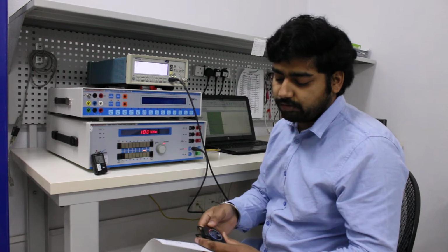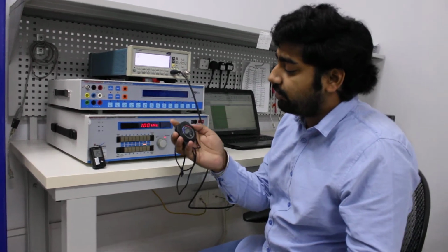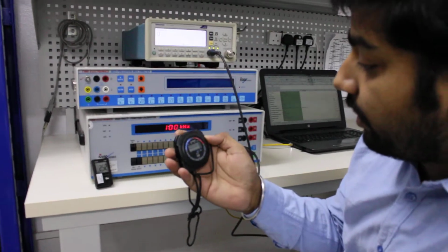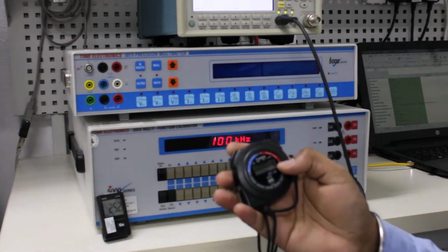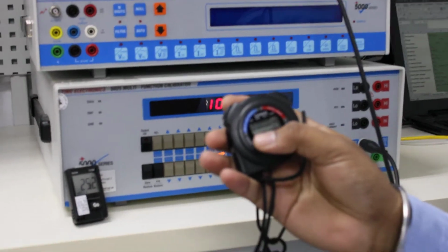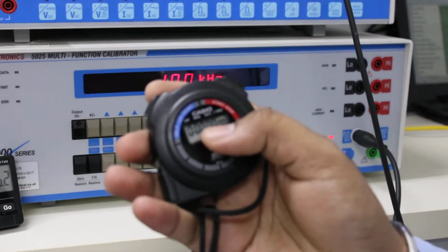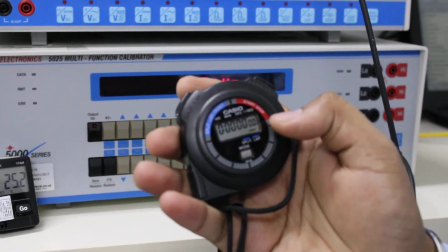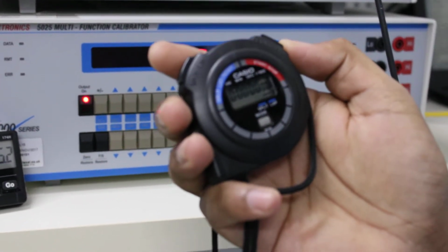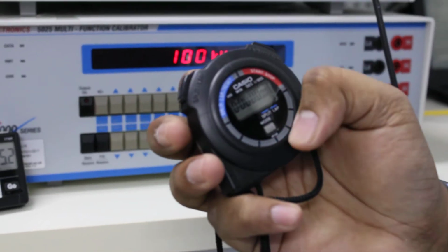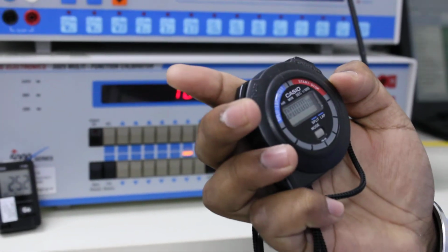I am working as a quality and production engineer. So today we are going to calibrate the stopwatch. The manufacturer is Casio, and the resolution is 0.01 second. As you can see, the display shows hour, minute, second and 1/100 seconds. This one has the start and stop function, and this one resets to 0.